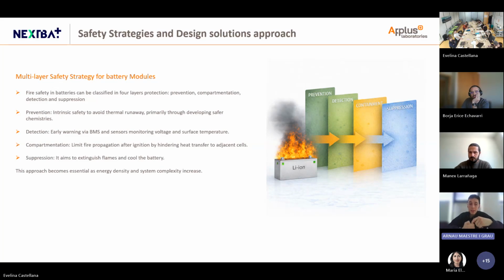Then detection, which relies on early warning via the BMS and additional sensors monitoring parameters. Then compartmentation, which aims to limit fire propagation by reducing heat transfer between adjacent cells or modules. Finally, suppression targets flame extinction and battery cooling once thermal runaway occurs.